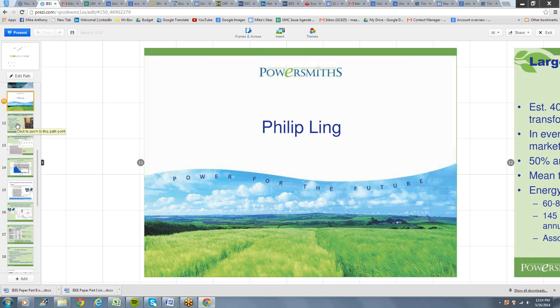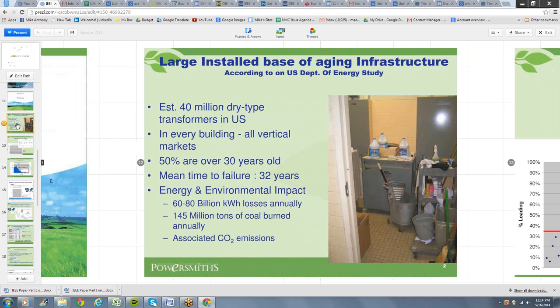Thanks, Mike. All right, I'm happy to talk to you a little more about transformers. Transformers, as you can see on this next slide, you really don't get a whole lot of respect. They're tucked in a closet behind locked doors, and on the bright side, they don't need a lot of maintenance, and that's kind of why they get forgotten. But on the flip side, they're actually burning a substantial amount of losses, and as a function of that, it's costing us money that we're not thinking about exactly because they're tucked away in these closets. There are a whole lot of these low voltage dry type transformers. The DOE estimates around 40 million of them.